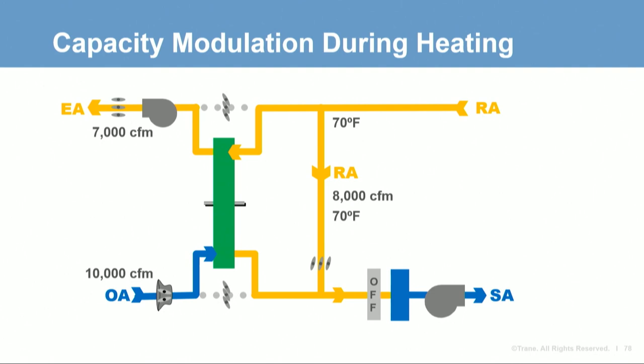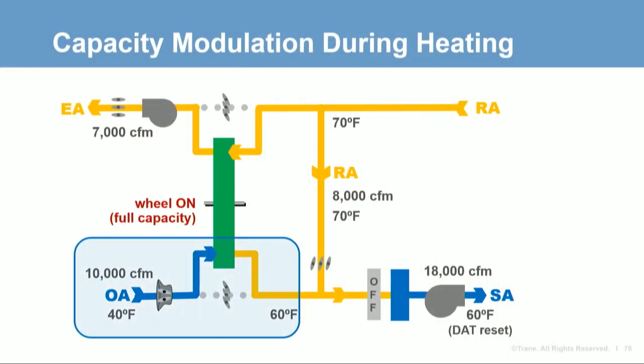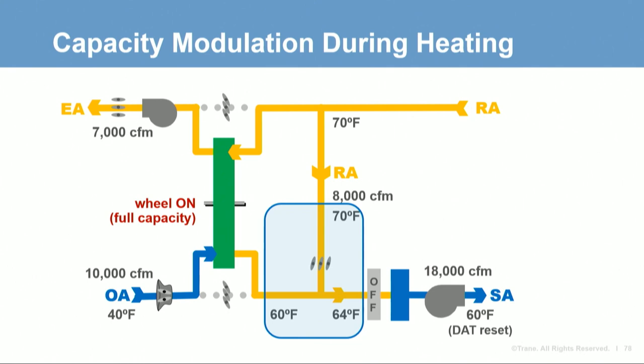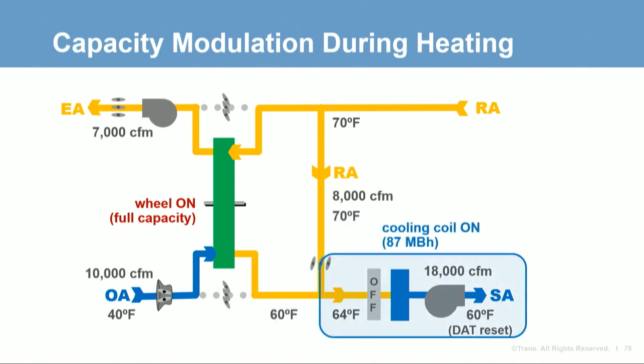Looking at the same example system at a cooler outdoor condition of 40 degrees: the VAV system is delivering only 18,000 CFM of supply air, and the discharge air temperature set point has been reset up to 60 degrees. If the energy recovery device continues operating at full heat recovery capacity, it transfers heat from the warmer exhaust air to the cold outdoor air, warming it to about 60 degrees, with a resulting mixed air temperature of 64 degrees. Since this is warmer than the 60-degree set point, the cooling coil must activate to cool the air back 4 degrees — the energy recovery device just overheated the air, requiring recooling.